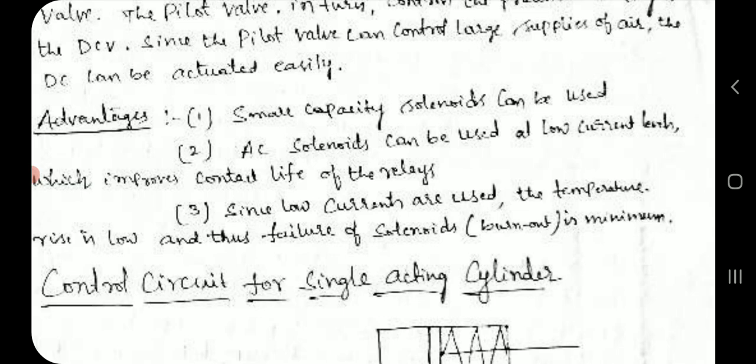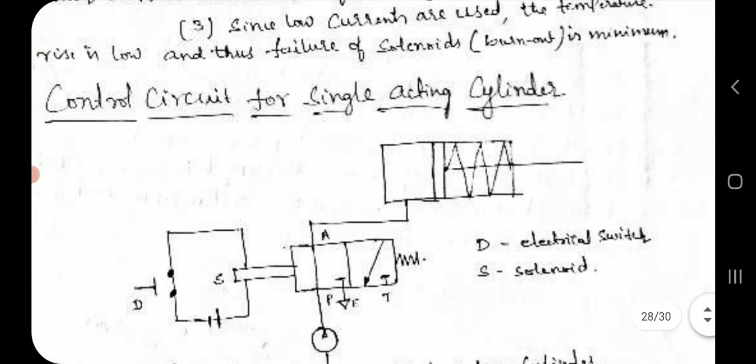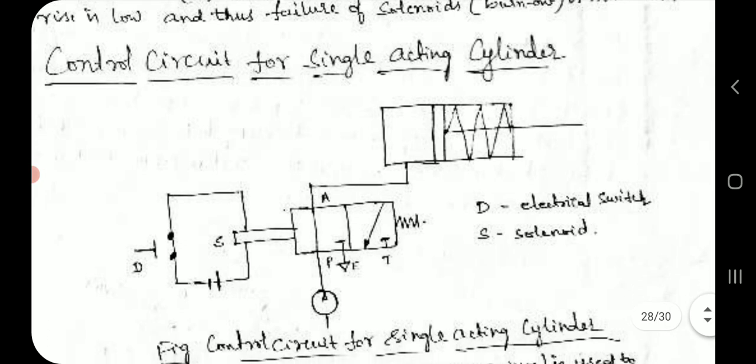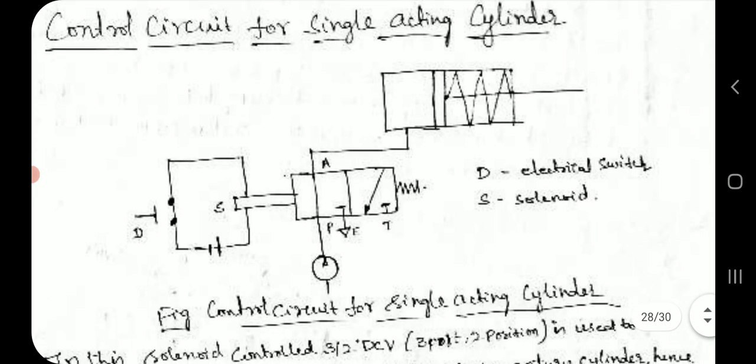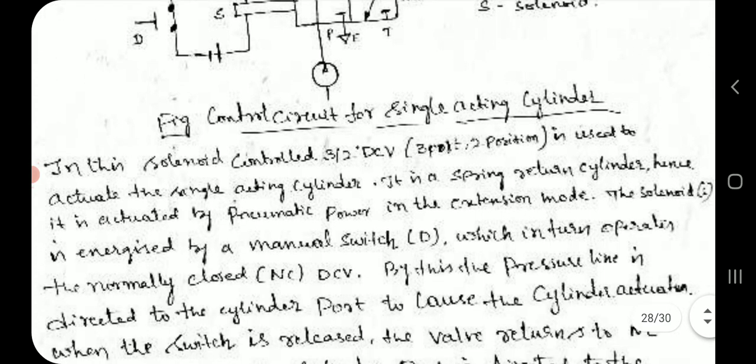Advantages: Small capacity solenoids can be used. AC solenoids can be used at low current levels, which improves contact life of the relays. Since low currents are used, the temperature rise is low, and thus failure of solenoids by burnout is minimum.